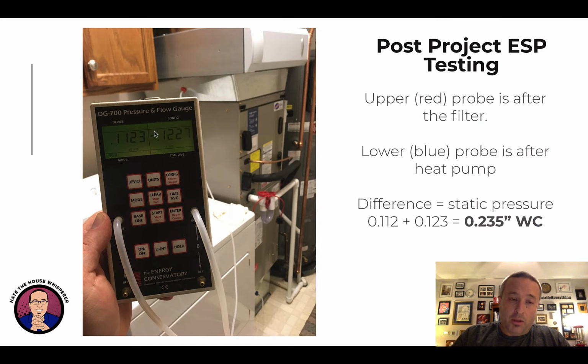And note how much lower these numbers are. If you add those two together, you get 0.235 inches of water column. So that's a super happy system, we're running at less than half of what the recommended high is. So this thing's crazy quiet.